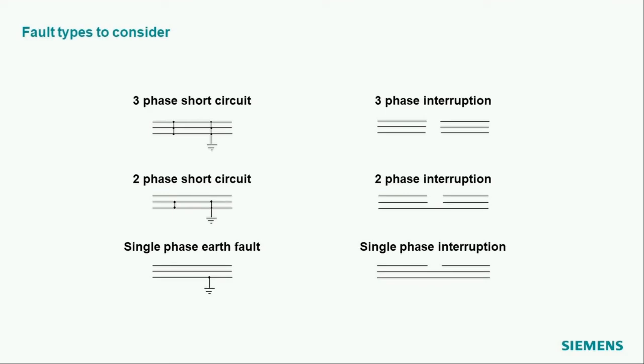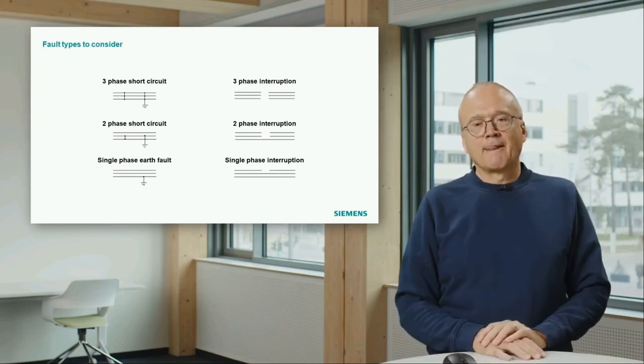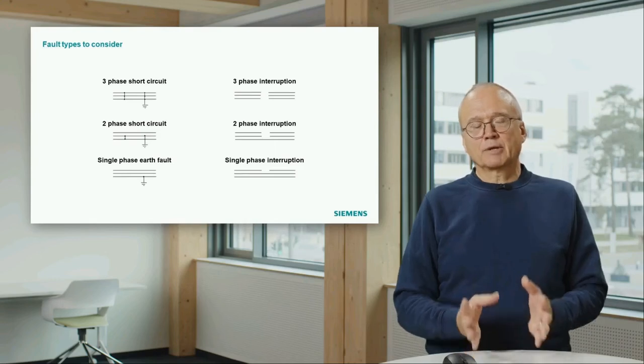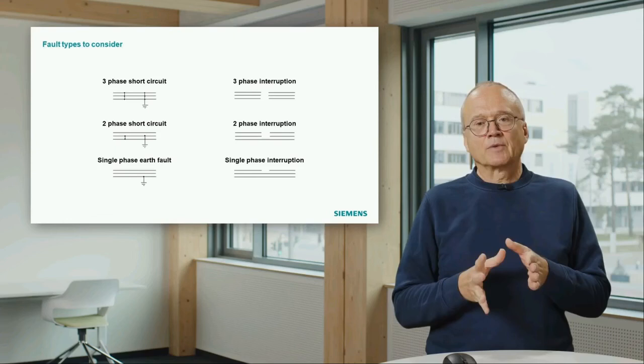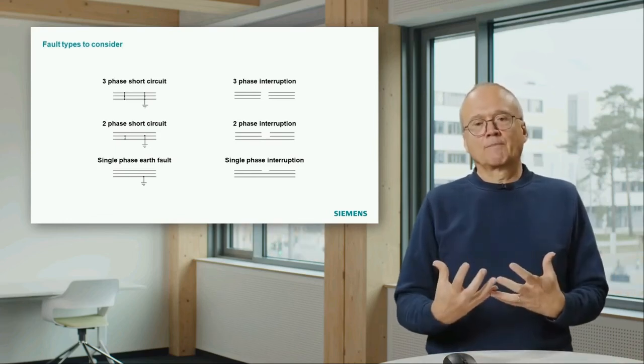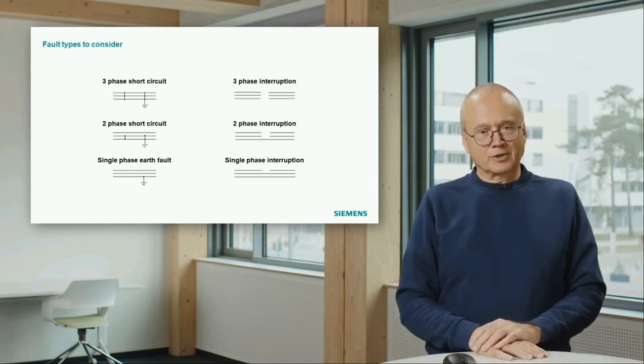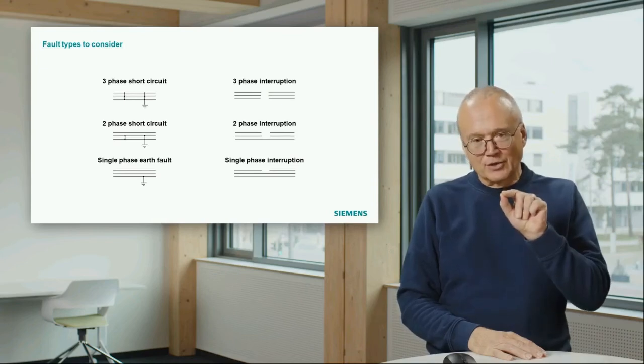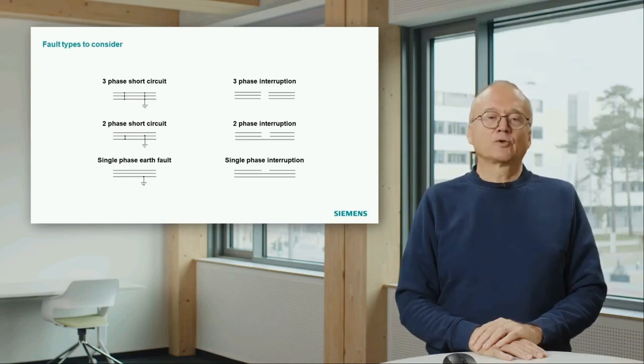On the right-hand side, you also see other types of faults like interruptions. They are not so critical normally. A three-phase interruption means we have no longer transport of energy. The other side is maybe without voltage, but it's not such a critical thing that something explodes. But if you, for instance, supply a big motor in a chemical plant and you have a single-phase interruption, a motor doesn't like that, or a generator, because these motors and generators need a three-phase system to have a constant torque. And if one phase is missing, you can destroy the devices.